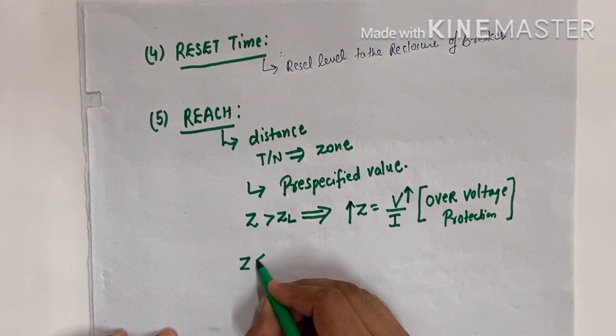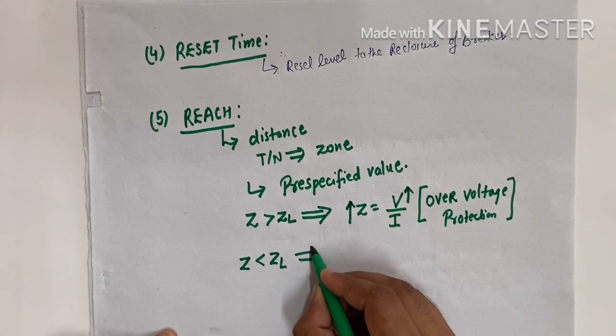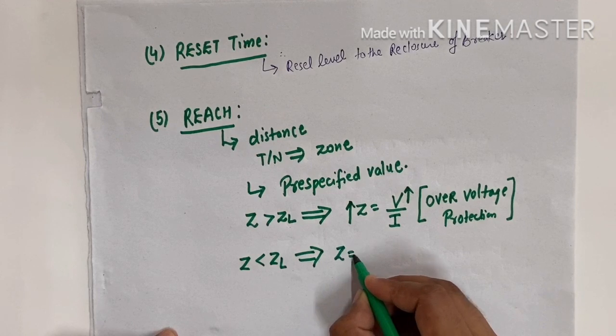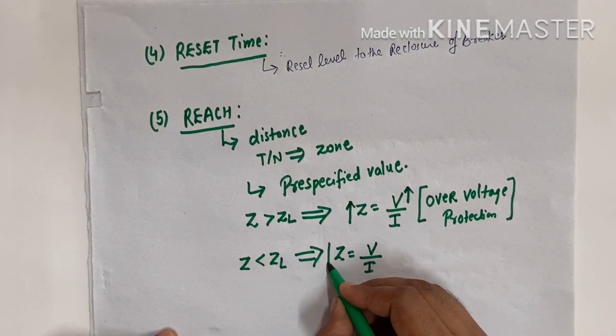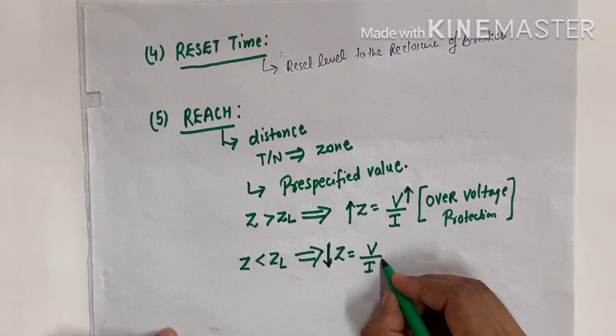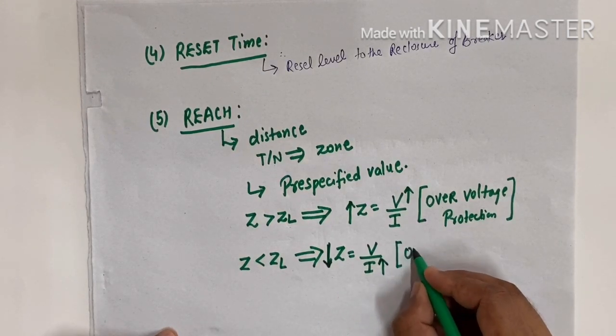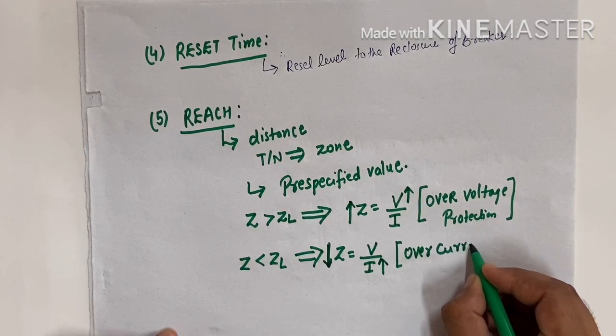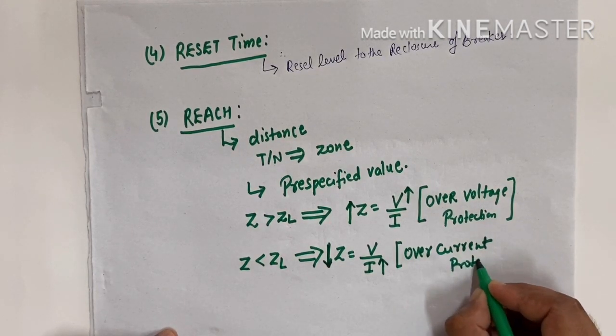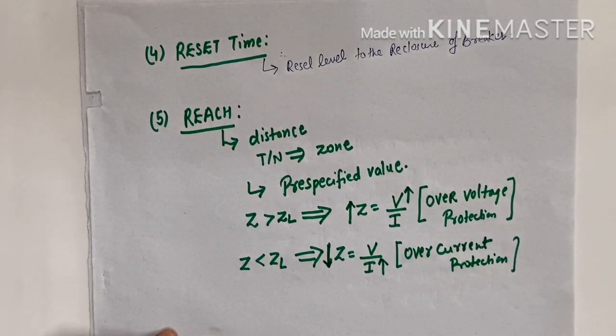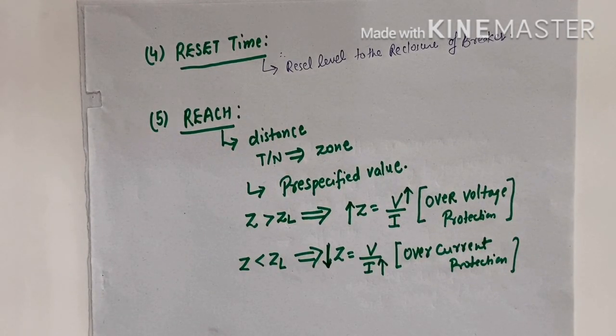Now if the impedance is less than ZL, Z equals V upon I, so if impedance is less, it means current is more. So this is used for over current protection. So in over voltage protection the impedance is greater than ZL, and in over current protection the impedance is less than ZL. ZL is the pre-specified value, the standard value that we set at the designing of the relay.